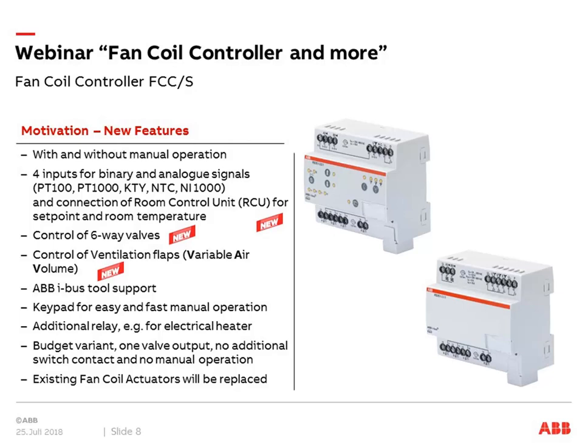Beside the outputs already mentioned, we have four inputs available. These inputs can be programmed either as binary inputs to connect any contact, window contact, push button, or dew point sensor, or as analog inputs to connect temperature sensors of different types: PT100, PT1000, KTY, NTC, and NI1000. Our room control unit RCU can also be connected. In the software you select between binary or analog functionality, and each of the four inputs can be parameterized accordingly.